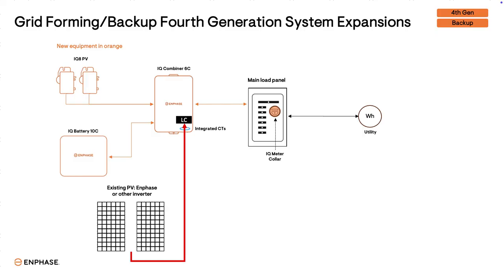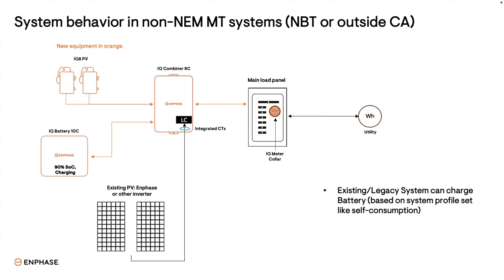With a future software update, the existing PV will be able to continue operating when the system is off-grid if sizing and design restrictions are met. The system will behave differently if it's a California NEM multi-tariff system versus a non-NEM multi-tariff system. Here's an example of system behavior for a non-NEM multi-tariff system such as net billing tariff or outside California. NEM multi-tariff rules don't apply, so the existing PV system can charge the battery of the expansion system and the PV system can export power to the grid. In this example, the expansion PV system and the existing PV system are producing a combined total of 4.7 kilowatts.